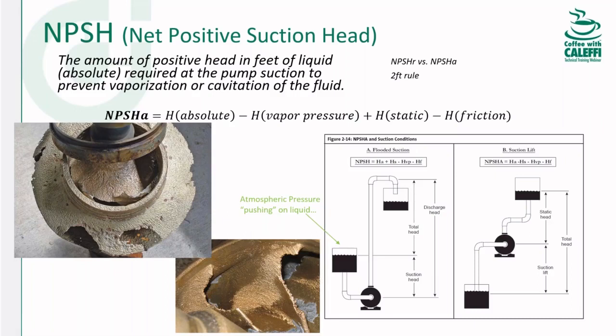You're probably going to be fine, especially if it's ambient temperature water. But on the suction lift, where the pump is pulling from a spot lower than the inlet, that's where you need to cross your T's and dot your I's. I don't know, Reece, anything to add to this?